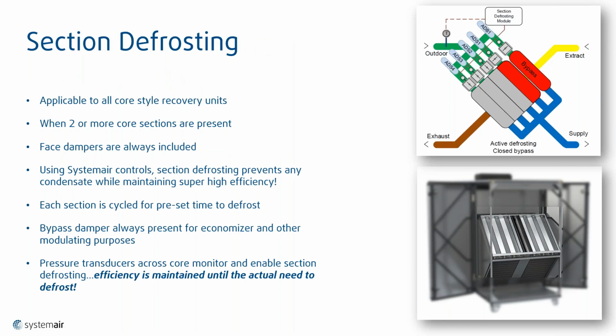Now for plate heat exchangers, as we all know, defrosting is a huge problem. There are lots of other systems and technologies out there. There's dual core, there's regenerative core, there's different ways where we could do it. One of the ways that we want to make sure that you get as much efficiency out of your core as possible at all times is we have section defrosting, which we can add on as an accessory to the actual core. What that does is it's dynamic defrosting. So that means that you're not flip-flopping the airstream every 60 seconds by default, whether or not you need to defrost. We put pressure sensors over each one of the dampers, which are individually controlled, and we measure the actual pressure drop through each one of those chambers to see what the pressure is from the frost buildup.